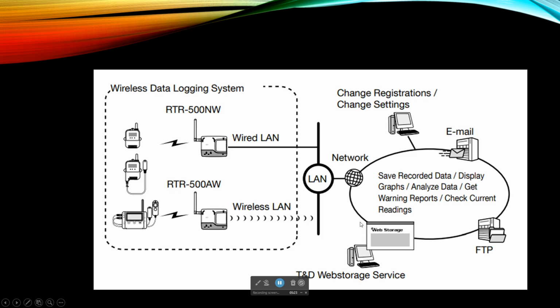Here's a schematic of the whole network of the RTR system. This unit is the network base station, which can be either wired or wireless, and they can receive signals from the data loggers, then they're connected to your LAN, where this PC is going to dictate the whole environment where the devices are registered and all the settings are entered. From there, we configure various things like SMTP for email, FTP, and web storage. These are various ways that you can set up an alert system and a data recording system.